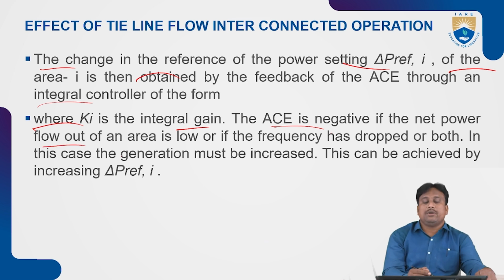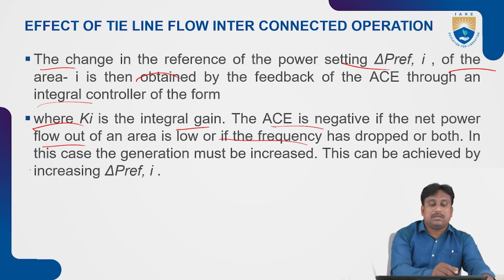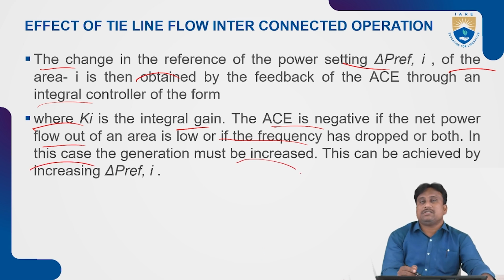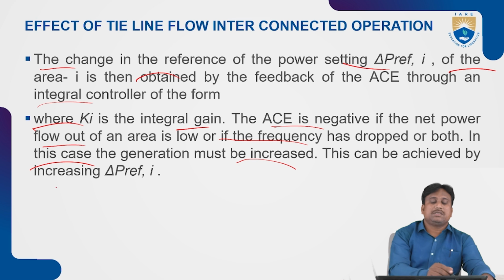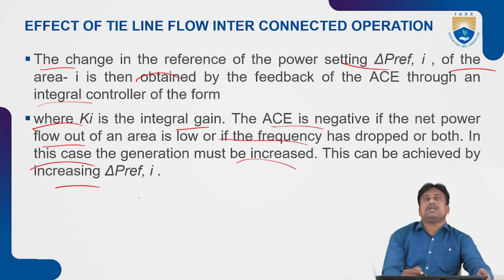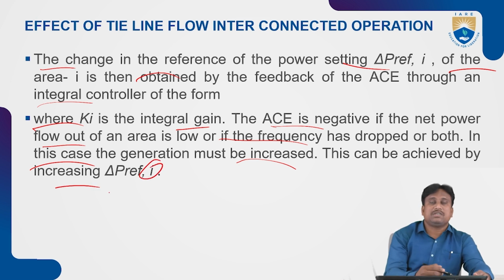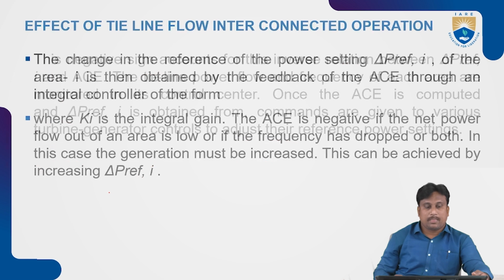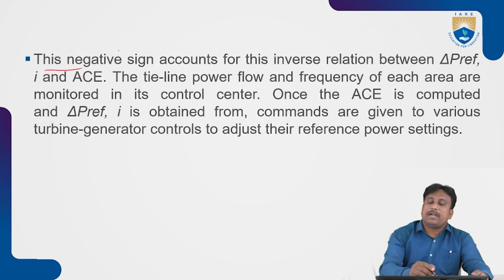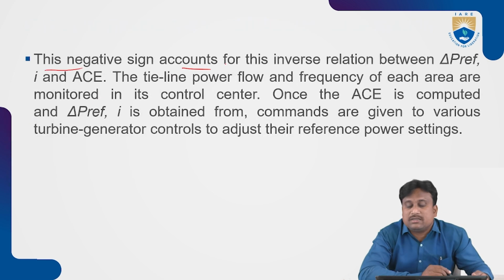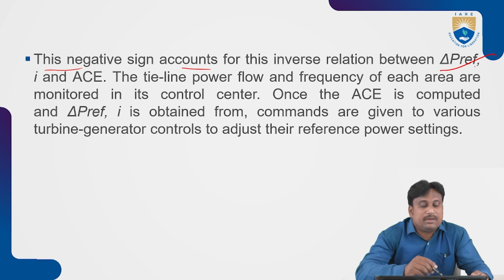If the net power flow out of an area is low, then frequency has drooped characteristics. In this case, generation must be increased. This can be achieved by increasing the delta P reference value to the extent of the area i. So this negative sign accounts for the inverse relation between delta P reference i and the area control error.